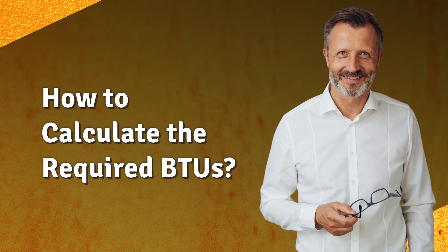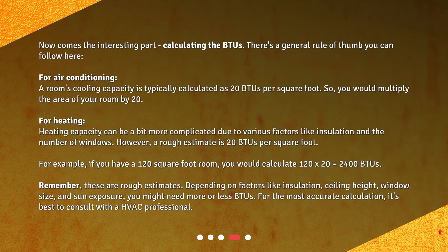How to calculate the required BTUs. Now comes the interesting part: calculating the BTUs. There's a general rule of thumb you can follow here. For air conditioning, a room's cooling capacity is typically calculated as 20 BTUs per square foot, so you would multiply the area of your room by 20. For heating, capacity can be a bit more complicated due to various factors like insulation and the number of windows. However, a rough estimate is 20 BTUs per square foot. For example, if you have a 120 square foot room, you would calculate 120 times 20 equals 2,400 BTUs.